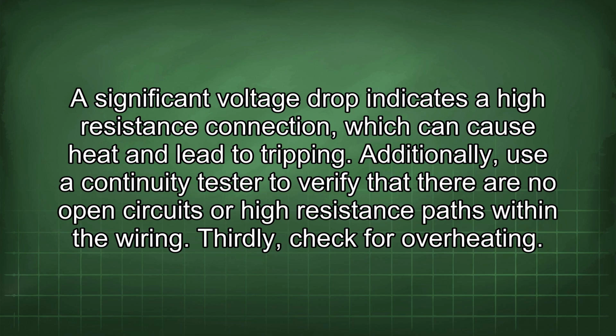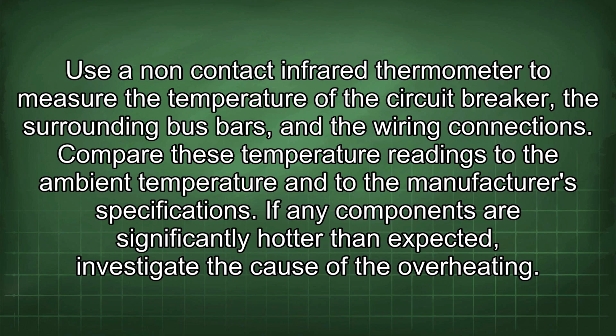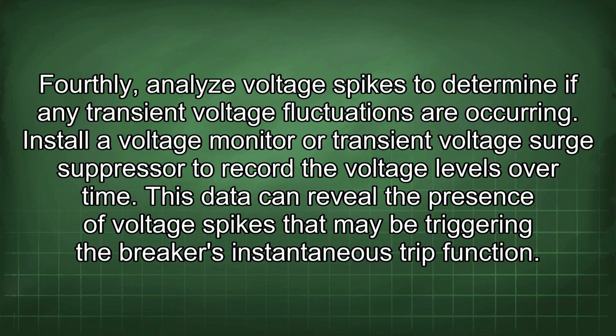Thirdly, check for overheating. Use a non-contact infrared thermometer to measure the temperature of the circuit breaker, the surrounding bus bars, and the wiring connections. Compare these temperature readings to the ambient temperature and to the manufacturer's specifications. If any components are significantly hotter than expected, investigate the cause of the overheating. Fourthly, analyze voltage spikes to determine if any transient voltage fluctuations are occurring. Install a voltage monitor or transient voltage surge suppressor to record the voltage levels over time. This data can reveal the presence of voltage spikes that may be triggering the breaker's instantaneous trip function.